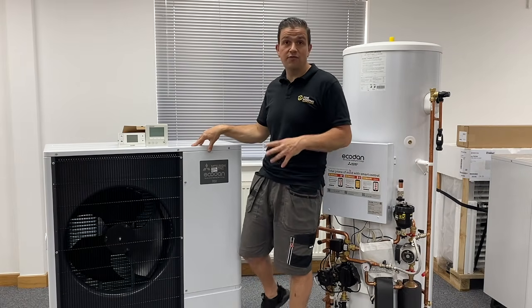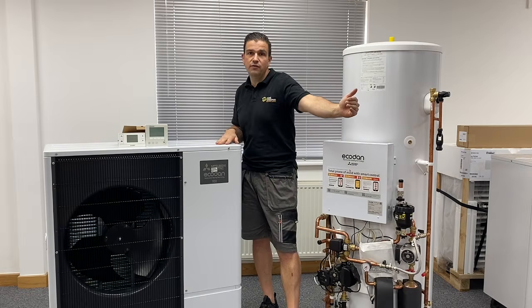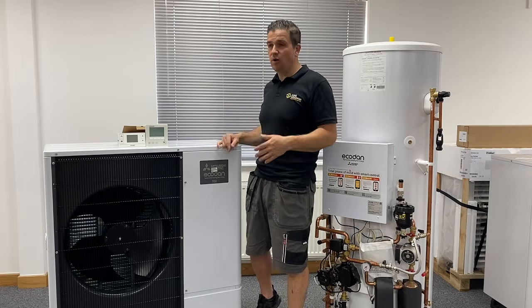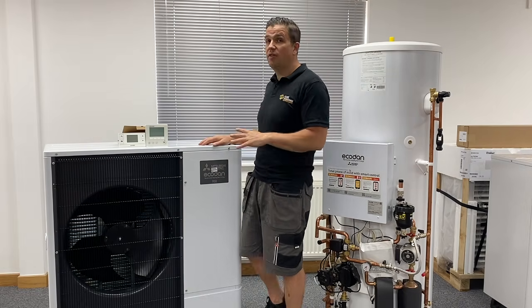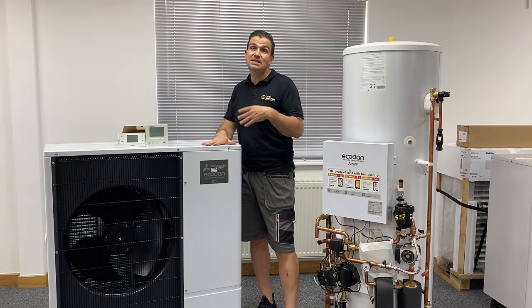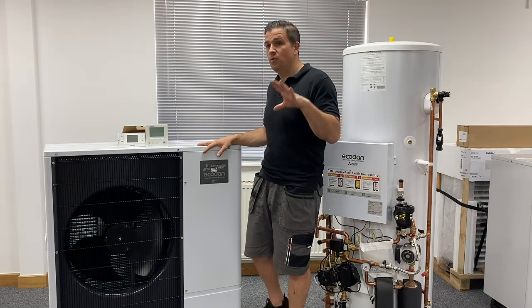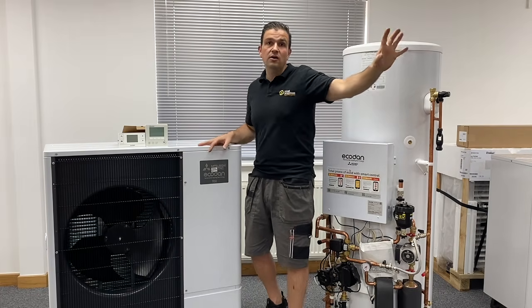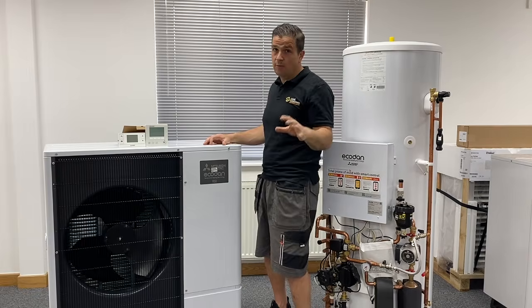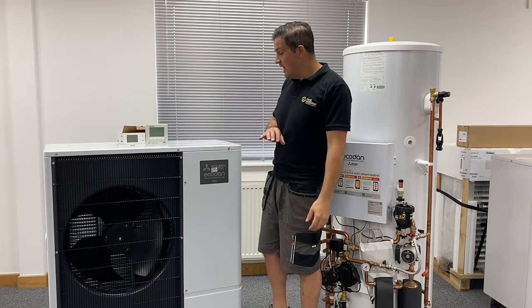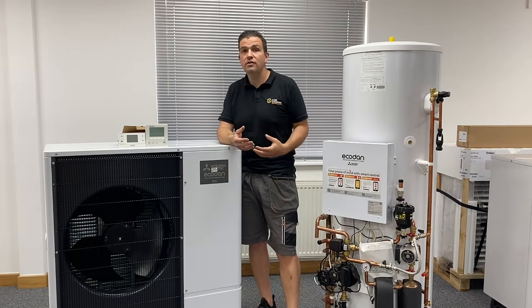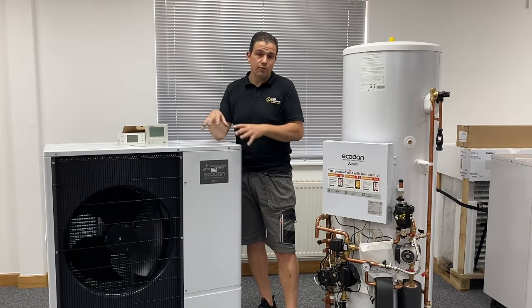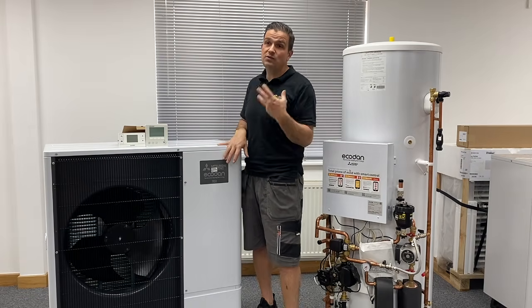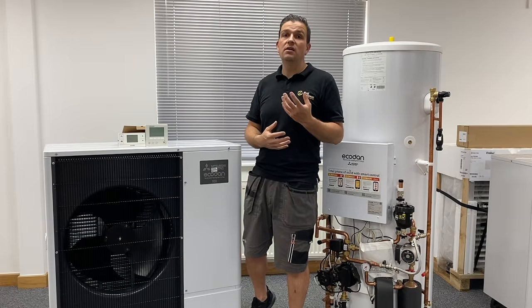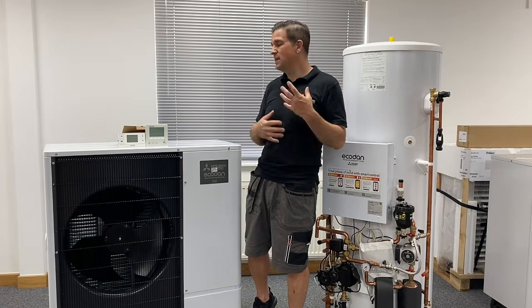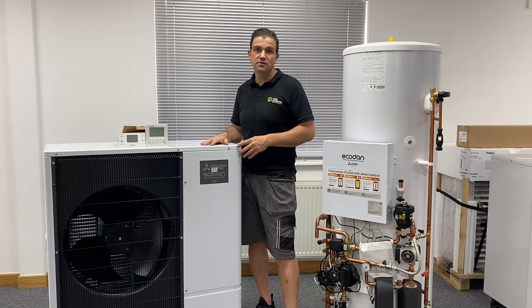Uses an R32 refrigerant now, away from the R410A. In comparison to 410A, the R32 refrigerant is kinder to the planet. There's less global warming potential, and we've got some figures and some other data on another episode which you can check out. We'll put it at the end of the video. And because it's a slightly different refrigerant, it's much more efficient. There's less refrigerant required for the heat pump, and therefore it will reach up to temperatures using less energy. So it makes it much more efficient for the unit to use.